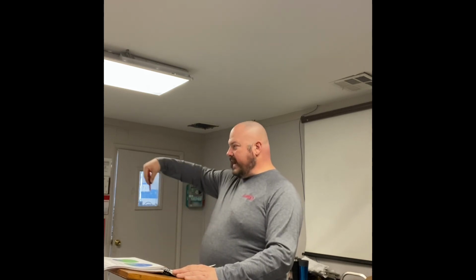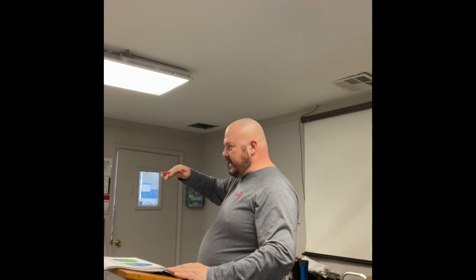But one of the things they do there at the warranty department is they cut that compressor in half, they pull the top shell off of it, and they look at the line in which the refrigerant has been settling. And you can see where the oil line is in there, and it'll have like multiple lines. It'll be over, under, mid, here, there, back. Okay, because so many different people put so much different levels of refrigerant in it. You can see that by how much oil is brought back to the system.